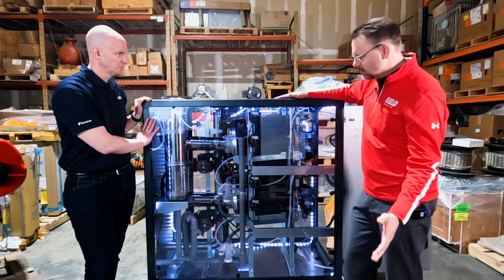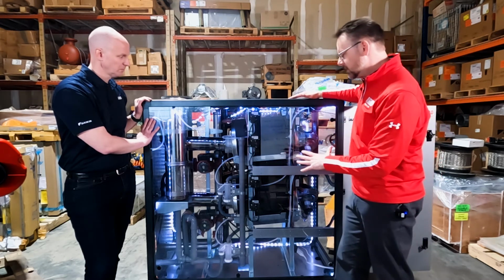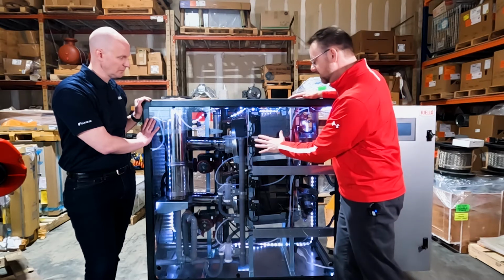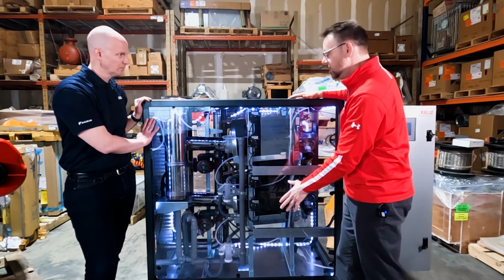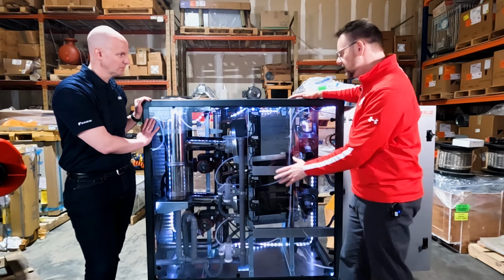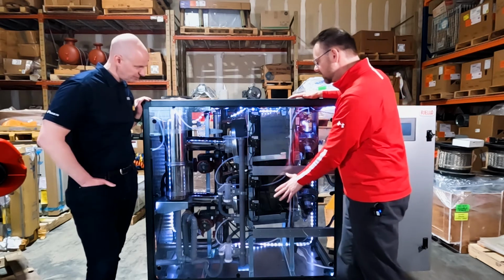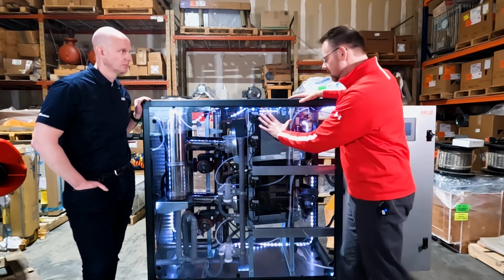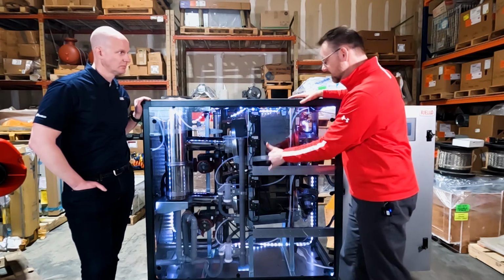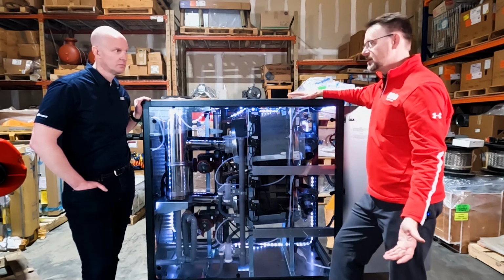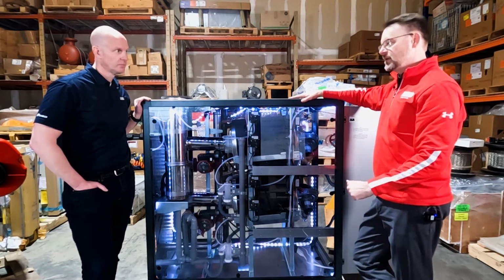So as you look at this, we're not doing two different things, we're doing the same thing twice in this cabinet. What we successfully do then is, instead of building an 800,000 BTU fired heat exchanger, we offer two 400,000 BTU heat exchangers to get to 800,000.